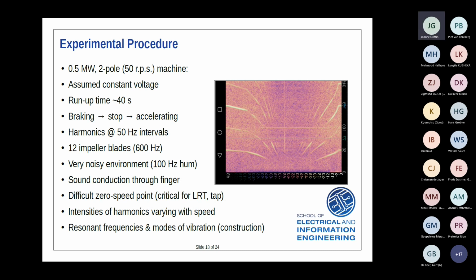After quite a few tests on the test bed, the test bed operator and I convinced ourselves that we could keep the supply voltage relatively constant, though I had no way of recording it this time. Luckily, this was a small machine compared to the test bed generator, which is in the order of megawatts, so we were fairly confident the voltage would stay constant - a fundamental assumption later in this work. The run-up time, from full speed backwards to full speed forwards, is about 40 seconds, quite a lot longer than the previous one I showed you. Just to show you what's happening, the machine is running.